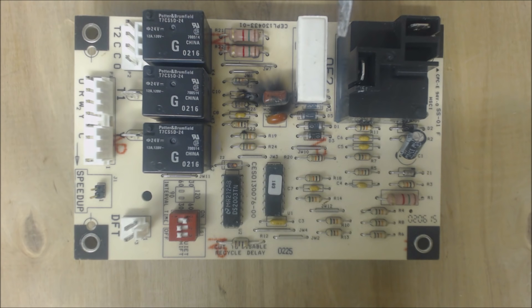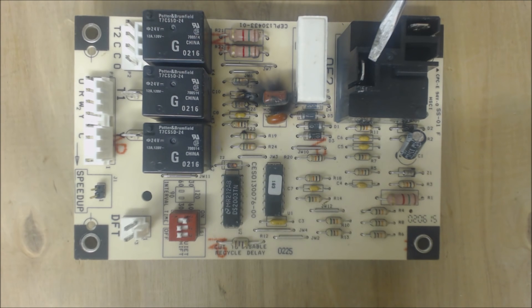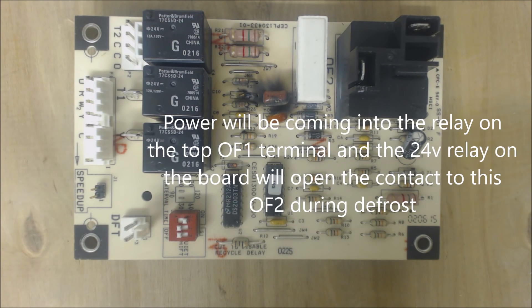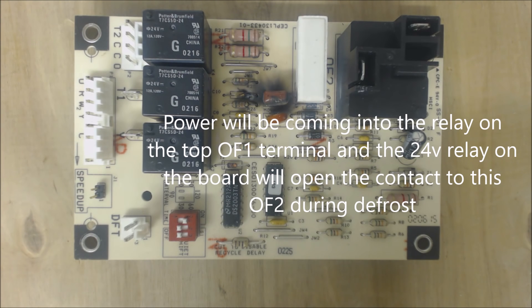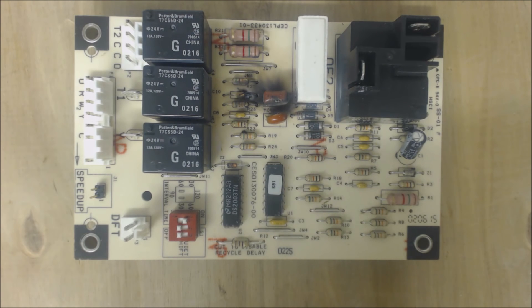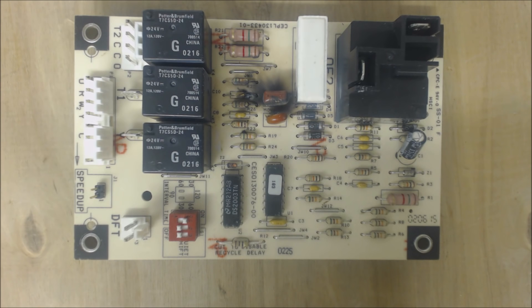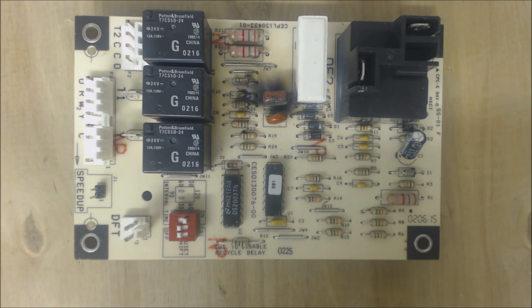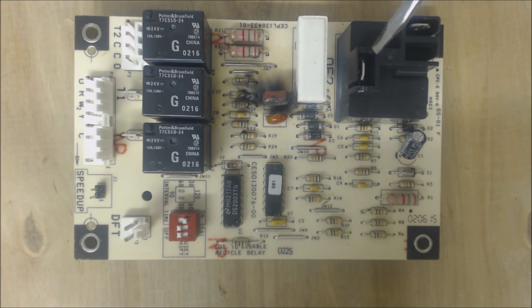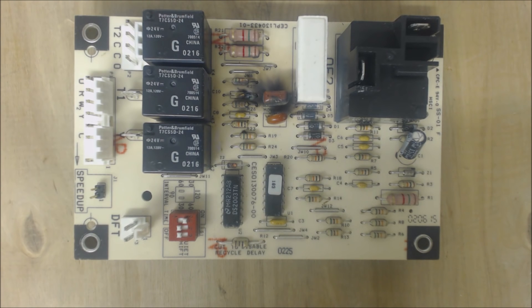Then you have OF2 and that powers the outdoor fan motor. So off of this relay here, the control board is powering the relay. It'll turn the outdoor fan motor off when it's in defrost because basically what's happening in defrost is you have the whole outdoor unit in air conditioning mode at that point. And in air conditioning mode, if you think about that, the fins are getting very hot. That's where it's rejecting the heat to the outside air. So typically, basically what's happening is in the middle of summer, the coil actually has to be a lot hotter than the outdoor air in order to reject the heat from the refrigerant. So that's how it ends up melting the coil. It ends up just heating the outdoor fins up and melting the frost off the fins. During that time, it shuts off the outdoor fan motor so that the coils just get relatively hot.